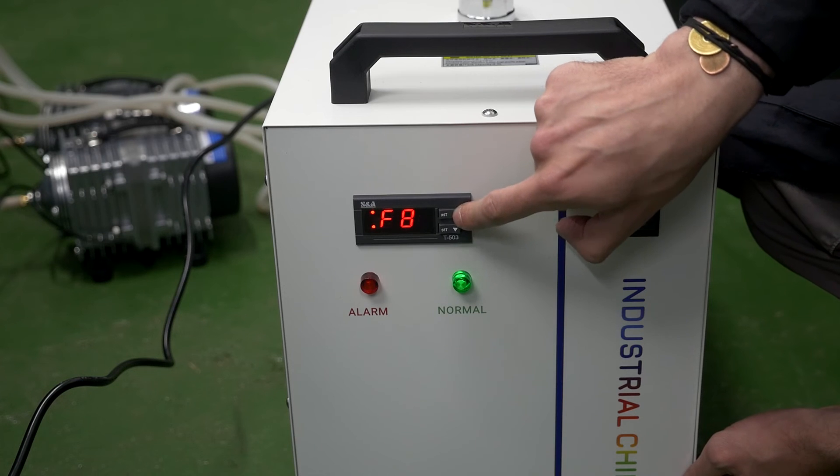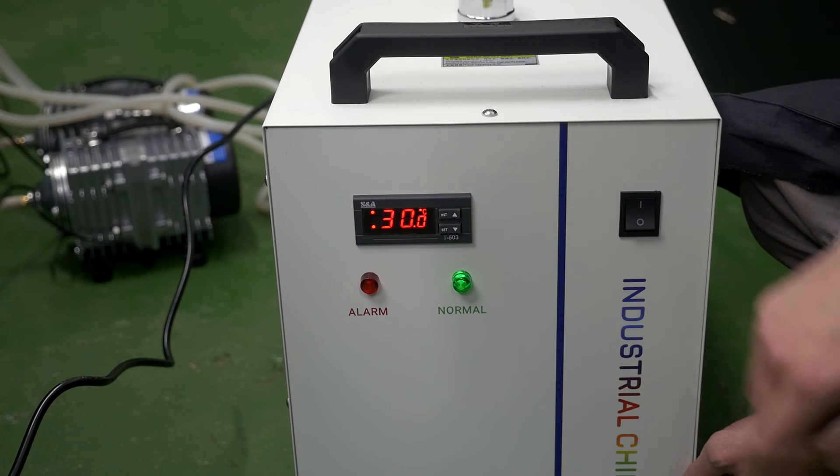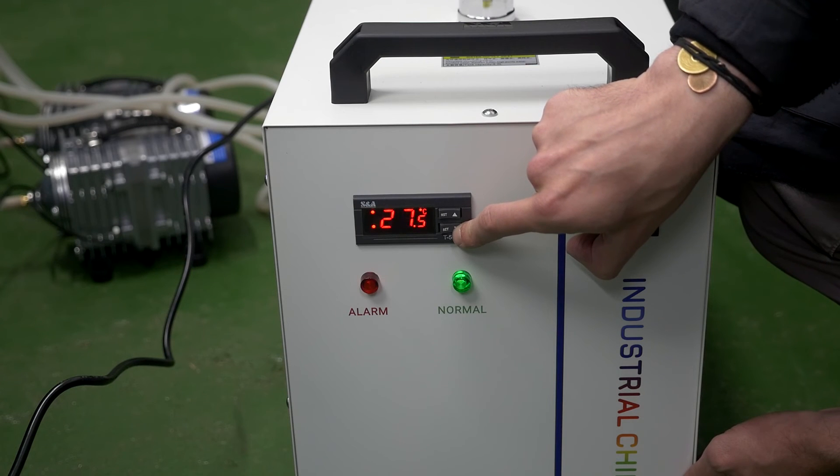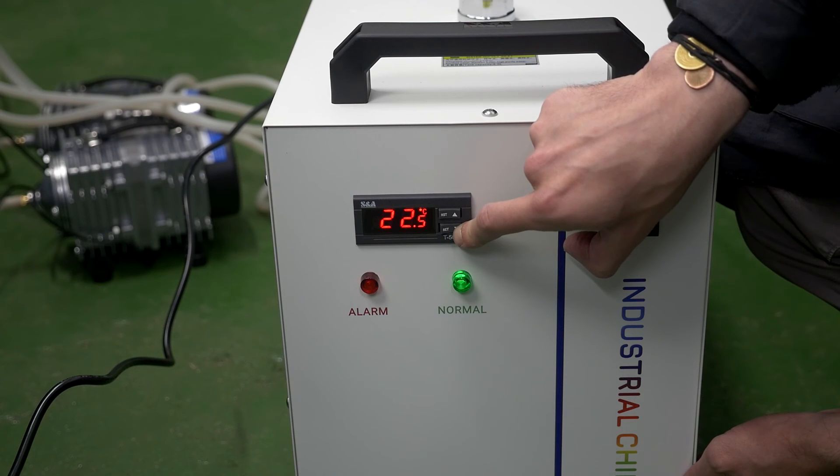Select F8 and press set. Set the value in the range 18 to 25 and press set. This parameter sets the upper limit value for the water temperature in the chiller.